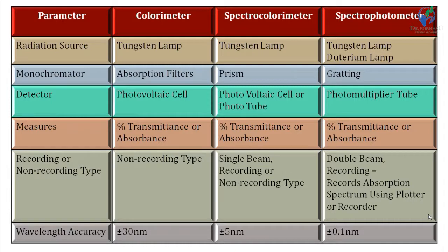For the detector: in colorimeter a photovoltaic cell is used; in spectro-colorimeter, PVC or photoemissive tubes are used; and in spectrophotometer, a PMT (photomultiplier tube) is used. The sensitivity increases in the order: photovoltaic cell, then photoemissive tube, then photomultiplier tube. In spectrophotometer, all components of highest efficiency and sensitivity are used, which is why spectrophotometers are the most accurate and reliable.